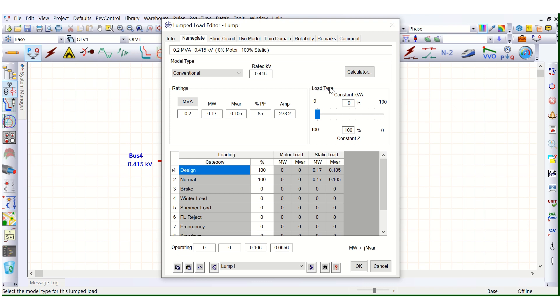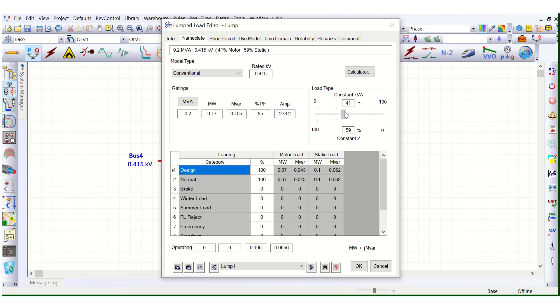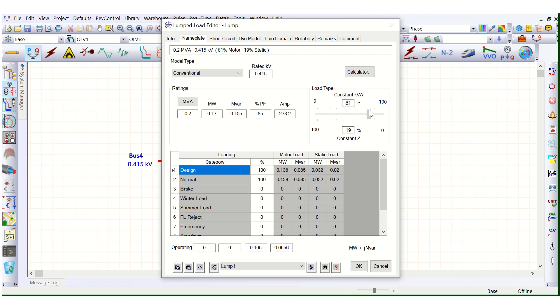This explains how ETAP software calculates current for each load type. Based on the actual loads in your project, you can assign what percentage is constant power load and what percentage is constant impedance load, and model the lump load accordingly. Hope that's clear.